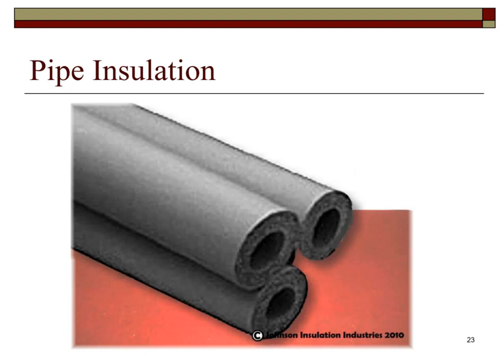Pipe insulation is shown here. The most common type of pipe insulation used in solar systems is a closed cell, flexible, elastomeric foam type rubber, commonly marked as Rubatex or Armaflex. Plastic insulation such as polystyrene or polyethylene should never be used due to their low operating temperatures. All external piping insulation must be protected from environmental and ultraviolet ray degradation by using special ultraviolet ray-resistant coatings, paints, and/or shielded wrappings.